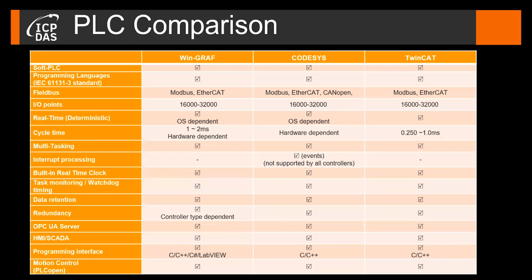Now, I often get the question from customers, what is the difference between an ICPDAS PLC and a PLC like Codesys or TwinCAT? First of all, all three PLCs are software PLC types. Soft PLCs are designed to run on a standard industrial PC with a Windows or Linux OS with real-time OS extension. Traditional PLCs, such as Siemens, Allen-Bradley, or Schneider, are hardware-based PLCs. They are designed to directly run on a CPU or hard real-time operating system. A hard PLC is a closed system and its functionality cannot be flexibly extended.